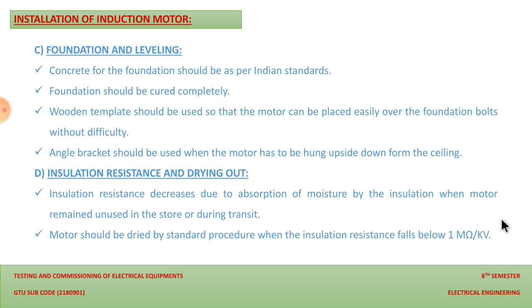When the insulation resistance falls below 1 megaohm per kV, we should perform a drying out process of the machine, because if the insulation resistance is reduced below 1 megaohm, we can say it has already absorbed moisture from the surrounding atmosphere. So its insulation resistance will become degraded, and we need to perform the drying out process to achieve the required insulation level of the conductors and the current carrying parts used inside the machine.